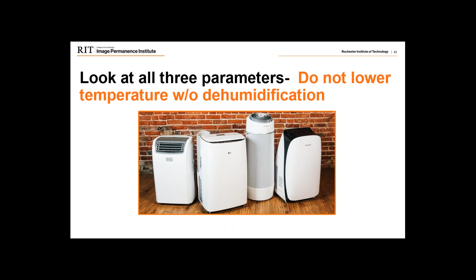It's warm for human comfort. We don't want that, we want to knock that down a little bit, so we bring in a portable air conditioning unit. The problem with those portable units is most of the time they do not affect dew point, they will not remove moisture from the air. Anytime we affect dew point, if we're reducing it, we're removing moisture from the air; if we're increasing it, we're adding moisture. Those portable units tend most of the time not to do this.